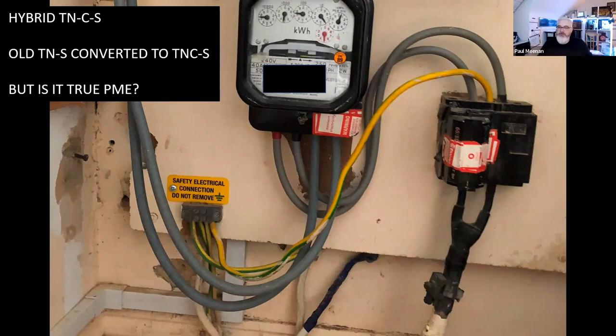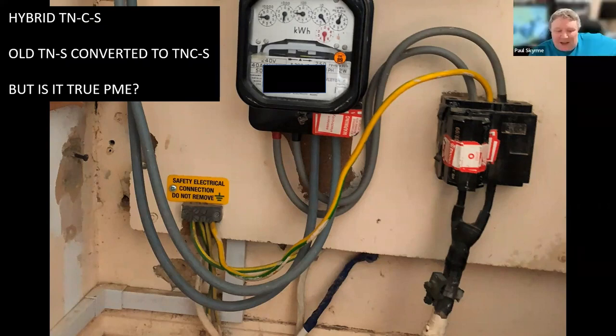I mean, strictly speaking, if we drop out of the DNO area now and come into 7671, for want of a better way of putting it, we've got an earthing terminal there. An earthing terminal for the premises, connected to a TNCS supply, with an extraneous conductive part coming in, which isn't bonded. Gordon nodded. Yeah, it's literally a shocker. Yeah, it is. You've got two different earthing systems, because obviously you're going to get a voltage rise and drop. There's going to be a voltage on a PEN and CNE conductor.